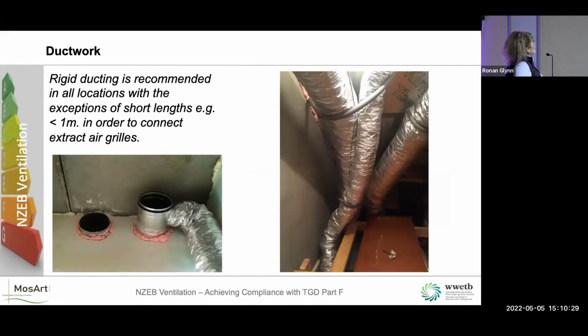So again, the installation commissioning guide and Part F state that rigid ducting is recommended in all locations, with the exceptions of short lengths, so less than a meter, just to connect up extract air grills. So as you can see here, I have two on the go now. This piece of flexible ducting has been shoved into the corner. So now it's at a right angle. So that's not a slow sweep and bend. So that fan there was going to have to work twice as hard to get the air out of that. Air flows like water. It flows in vectors. So if it hits a solid surface, it takes a lot of energy for that air to change direction and flow a different way. So by minimizing the number of bends and making them slow sweep bends, you're reducing your fan power. Again, this is another example of long runs of flexible ducting, which aren't really adequately bracketed up there either. The Northern Ireland regs say 300 mil, so they really hate this stuff. So 300 mil is all you're allowed in Northern Ireland.